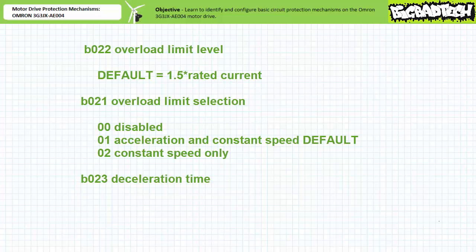B021 and B023 respectively dictate during which occasions active overload limitation occurs and how long it takes to decelerate the motor. The default state of the overload limit B022 is 1.5 times the rated current of 2.6 amps, or 3.9 amps. Protection parameter B021 has three options: 00 disables active overload limitation at all times; 01, the default, enables it during acceleration and constant speed mode; and 02 enables it only during constant speed mode. Protection parameter B023, deceleration time, is the time span of the deceleration event — the default setting is one second.